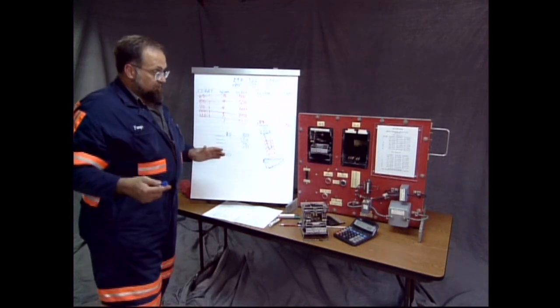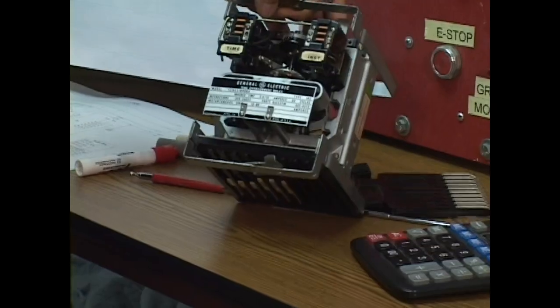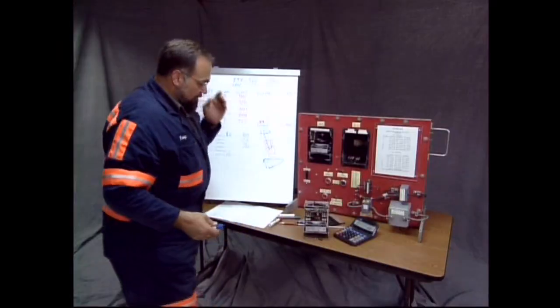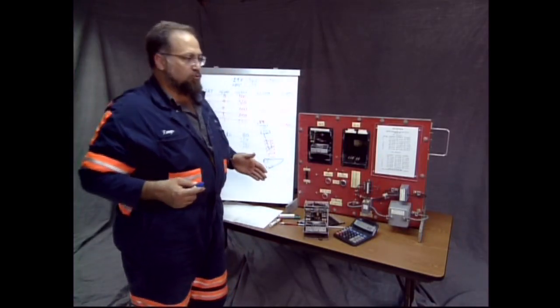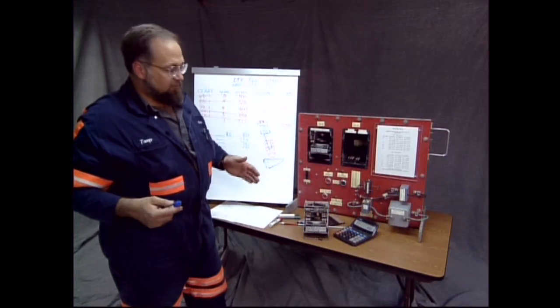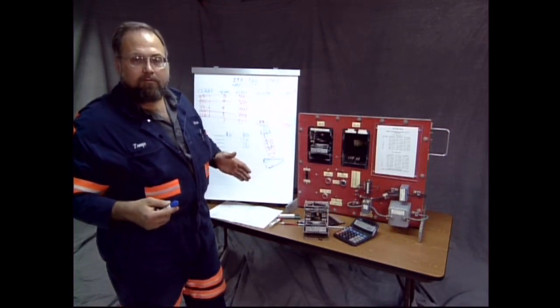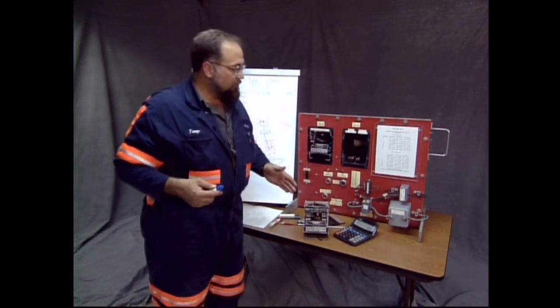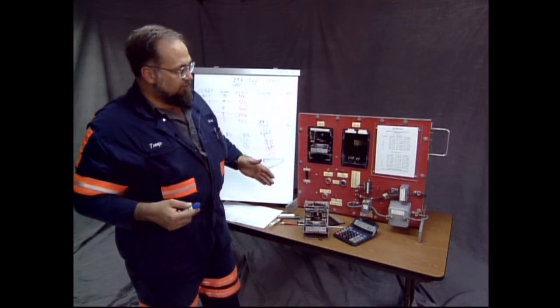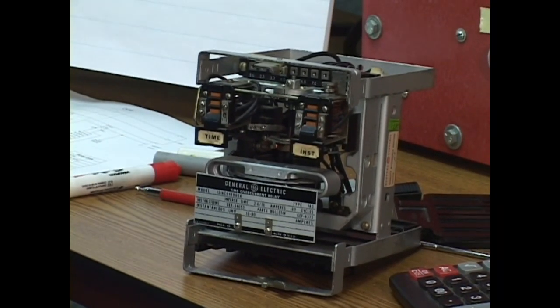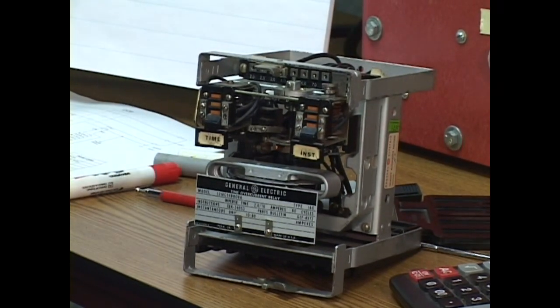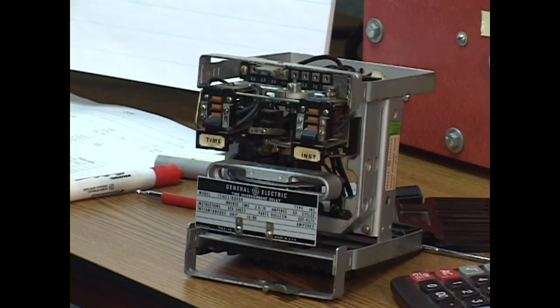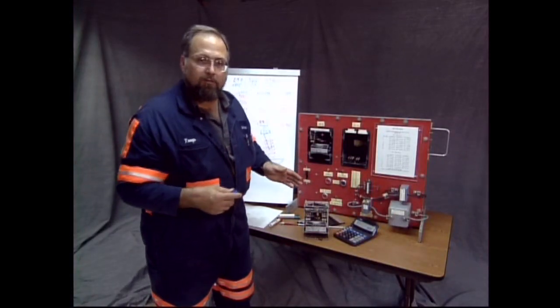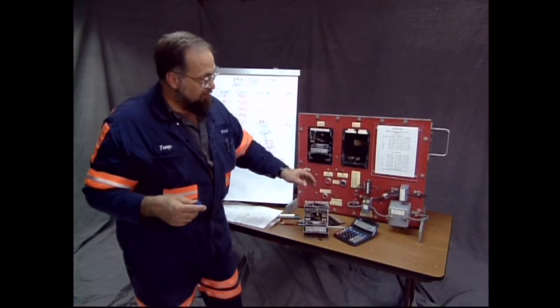How much? There's only two markings on this device. One says min, one says max. On the tag, it says 10 to 80. Now, the only way to truly adjust this relay, because every relay is not just like another one, is to use a current generator and actually drive the CT, put a current on the CT and operate the relay.